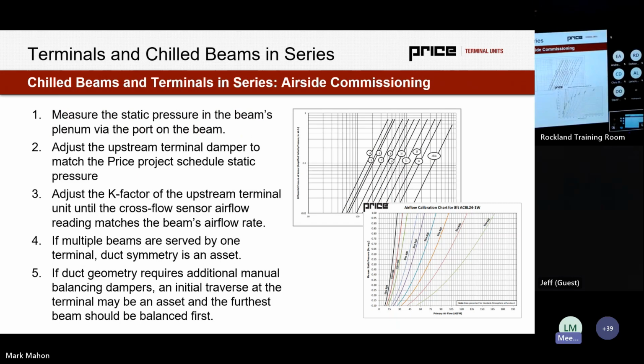So how do we do these two things in series? How do we rectify a VAV terminal and a chilled beam at the same time? There's a few different thoughts to this. I'm going to run through a couple of them quickly. So the first thing is we are still going to measure the static pressure in the beam's plenum via the port on the beam, and that's going to be the main way that we're measuring, testing, and balancing airflow. That at the end of the day is what we're trying to truly balance and control.